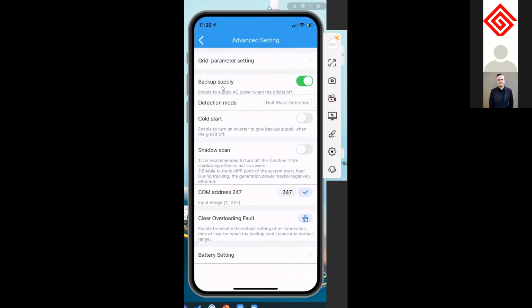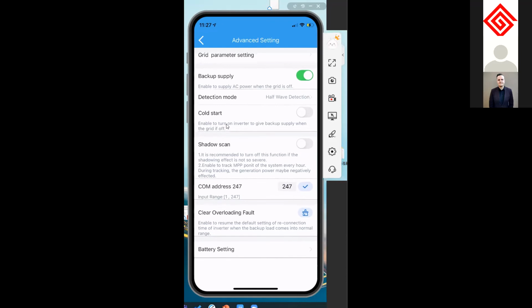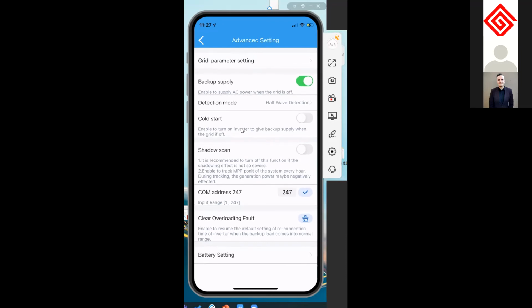And here you can activate the backup power supply. In case you want to use the backup loads, then you need to activate this function here. Detection mode, you can just keep as the standard, half-wave detection. Cold start is in case you want the inverter to turn on even if the grid goes out, during the night for example. Then the inverter needs to start up without the grid, and you can turn this one on here. Here you have the shadow scan, for example. Here you can put the COM address, and here is the clear overloading fault button.